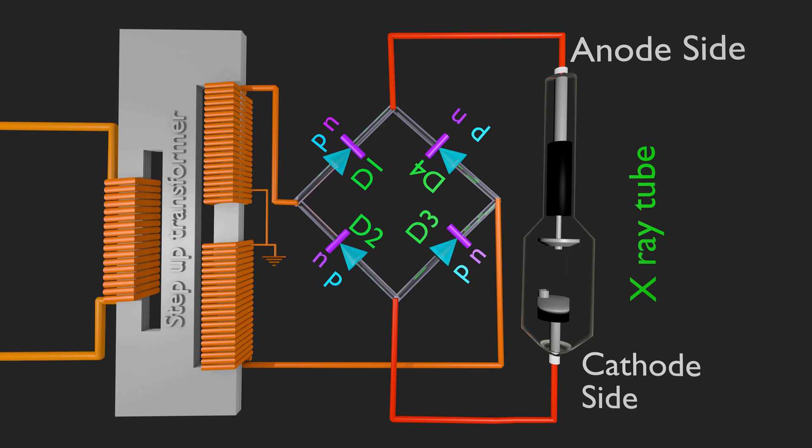Consider one half cycle of AC input when upper pole of secondary winding of transformer is positive in respect of lower pole. Here, diode 1 is forward biased as p side of it is connected to positive polarity. But diode 2 is reverse biased, as N side of it is connected to positive polarity. Hence D2 does not conduct. As D1 conducts, anode of X-ray tube gets positive polarity.